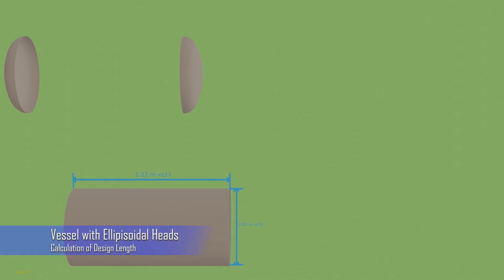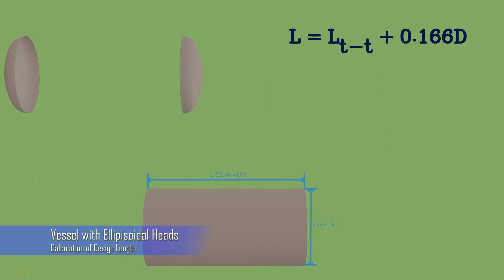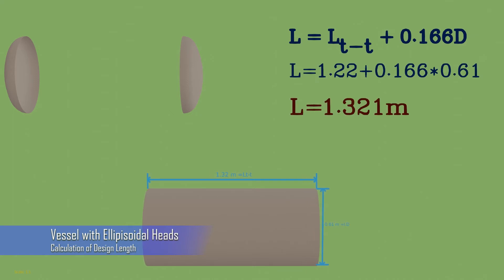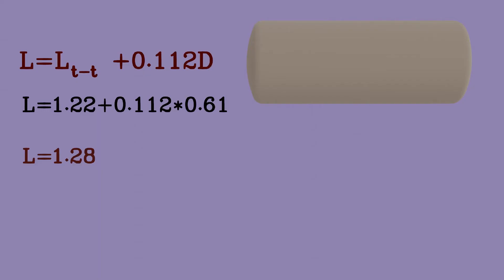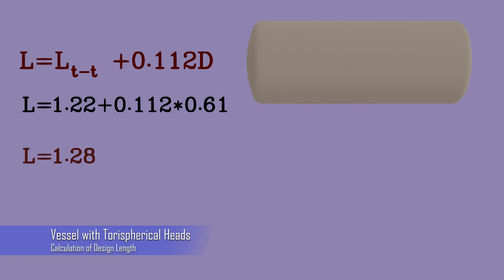For a vessel with an ellipsoidal head, the design length is L = Ltt + 0.166 D. Inserting the same values of Ltt and D gives L = 1.321 m. For a vessel with a torispherical head, the equation is L = Ltt + 0.112 D, which gives a design length of 1.28 m with the same corresponding diameter of 0.61 m.